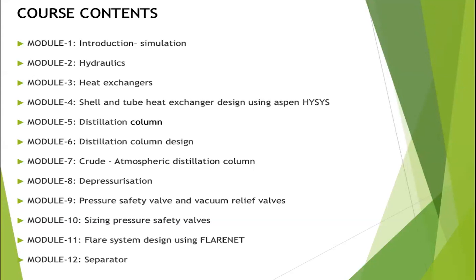Module 9 covers pressure safety valves and vacuum relief valves, including the design criteria and contingency analysis — the different overpressure scenarios. For vacuum relief valves, we'll use API 2000 techniques to design those valves.